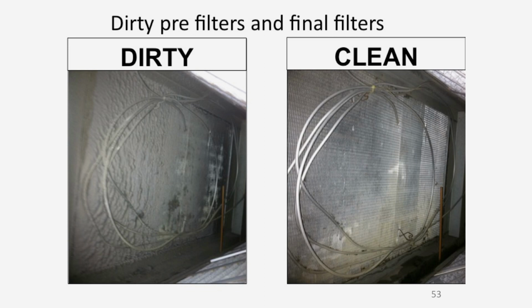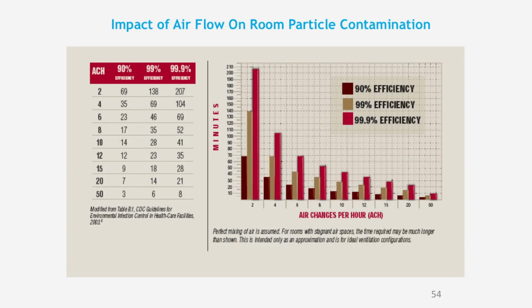And certainly we can show examples where decreased airflow can create problems within the building, because slide 54 is all about air change rates. If we can move air, if we can keep those air change rates up there, we can get rid of 90% of the particles in the air in just 12 minutes with 12 air changes per hour. The graphic on the right really shows that in a visual manner rather than numerical. And certainly that point of diminishing returns around 12 and 15 is more readily met when you've got the air to accomplish that task.